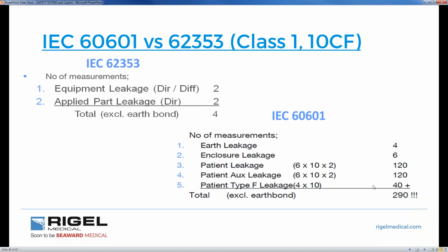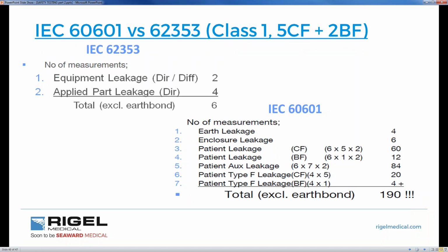I could do a factor of probably, within a day, maybe 50 times the testing with 62353 as opposed to 60601. That's something to bear in mind, when the whole purpose of the standard, as far as 62353 is concerned, is to make the clinical engineer or biomedical engineer's life a lot easier. Here's another example, class 1, if we have 5 CF, 2 BF, like a defib tester, for instance. We've got 190 tests if we use the 60601 standard, and 6 tests if we use the 62353. Clearly there's a big benefit as far as time is concerned.